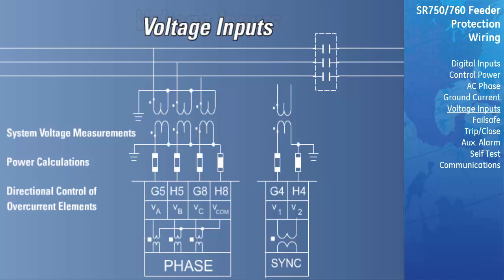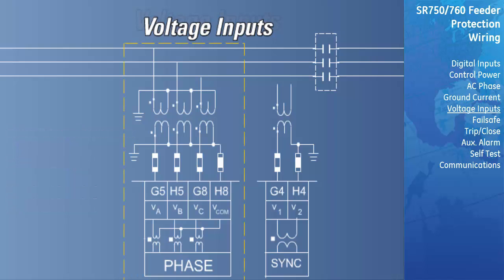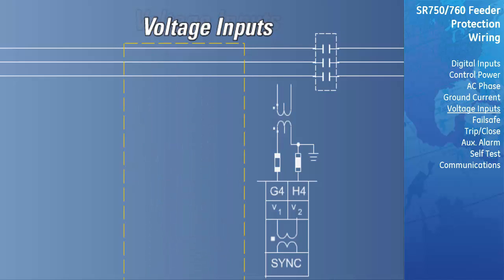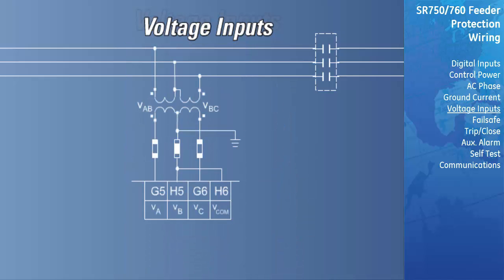There are 2 different wiring configurations for the bus VTs. A Y connection requires 3 VTs, 1 for each phase. This connection will provide line-to-neutral voltage measurements. An open delta configuration only requires 2 VTs and will provide phase-to-phase voltage metering. Line-to-neutral voltage cannot be measured and will not be displayed. The 750 voltage terminals are internally connected in a Y configuration. If an open delta configuration is chosen for the system VTs, the VB and VCOM terminals of the relay must be connected external to the relay.